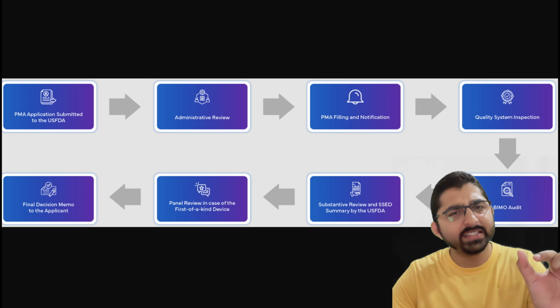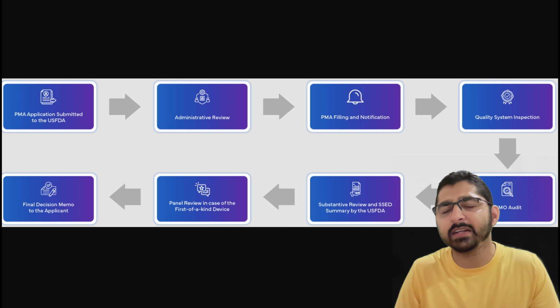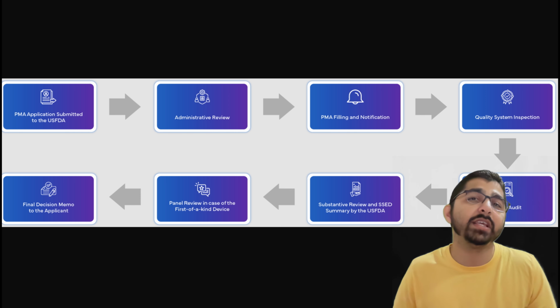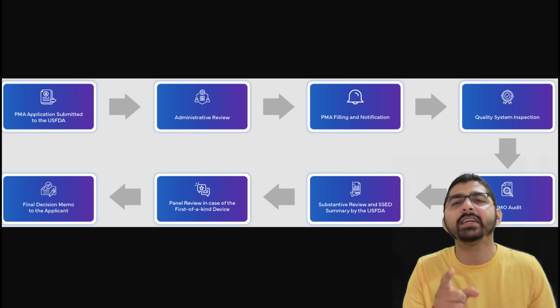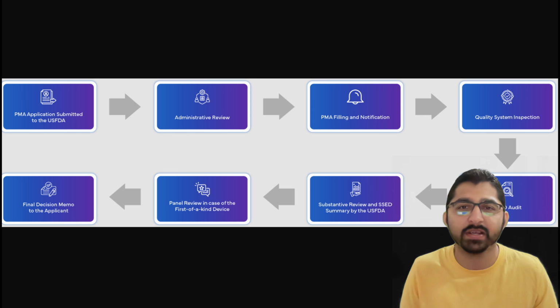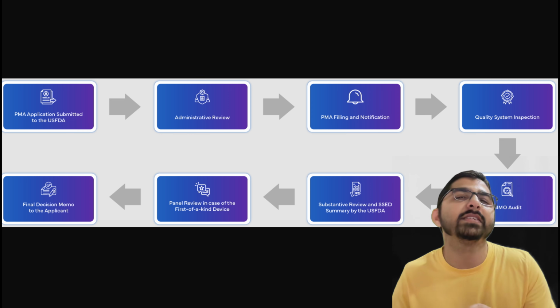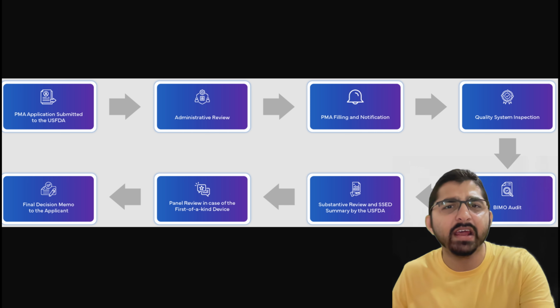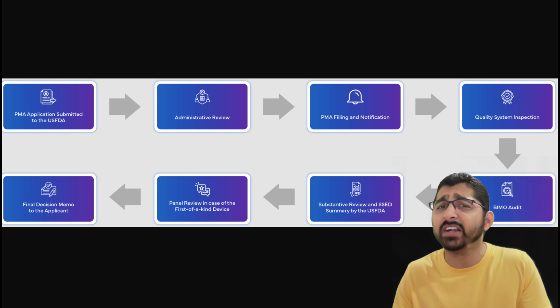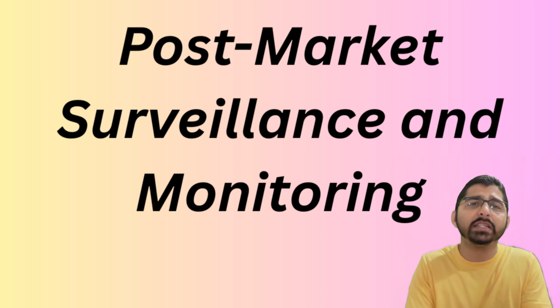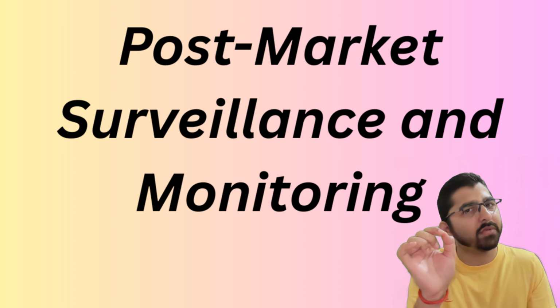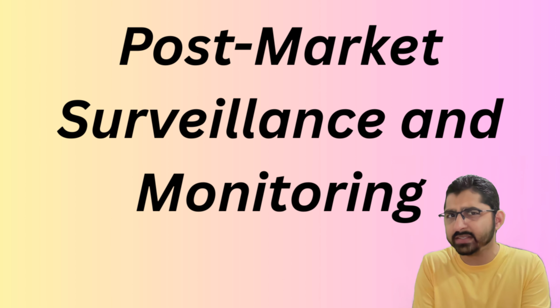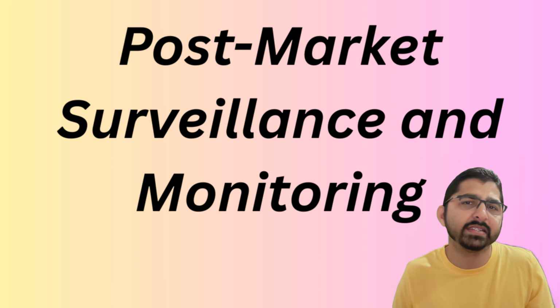So once your device is approved, it can be marketed and sold in the US, but the FDA continues to monitor its safety, my friends. So you need to keep this in mind. When I say that the FDA is going to keep vigilance, part 4 comes into the picture. What is this part 4? Part 4 is none other than PMS and monitoring. When I say PMS, it's post-market surveillance and monitoring.